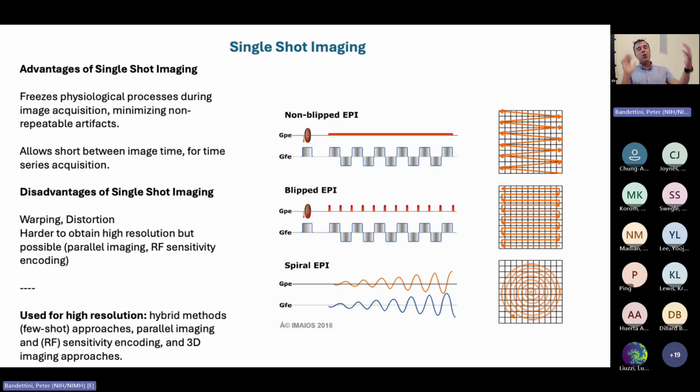When you go to high resolution, your signal to noise is low enough that physiologic motion-induced phase errors are about on the same order as your thermal signal to noise. So it's less of a big deal. That's why people like to do 3D. No one does 3D imaging at low resolution. They do 3D imaging only at high resolution.